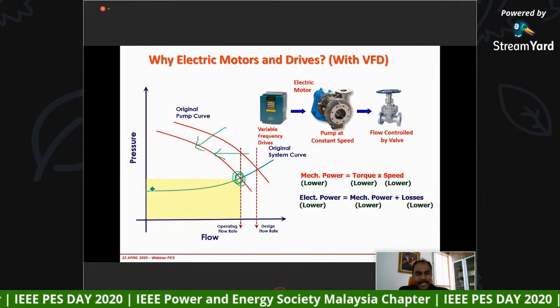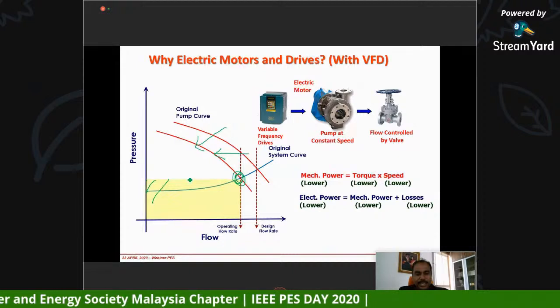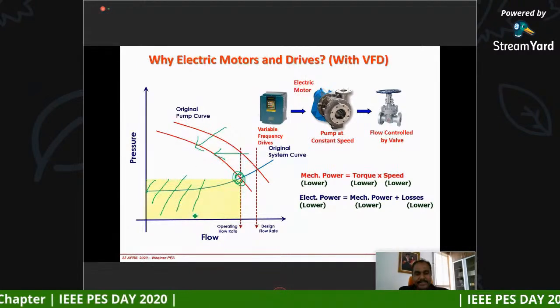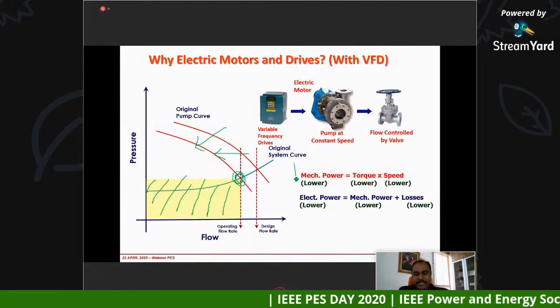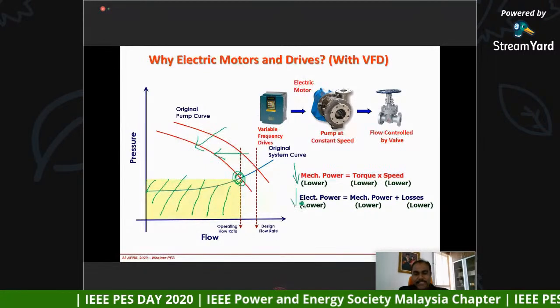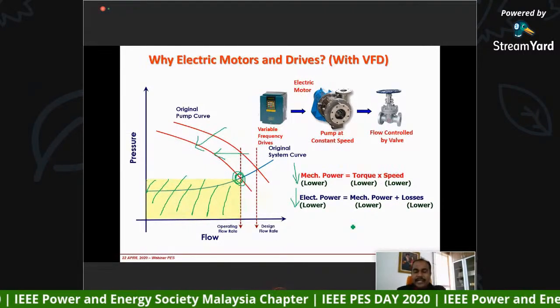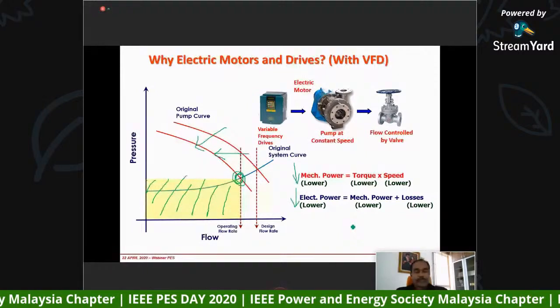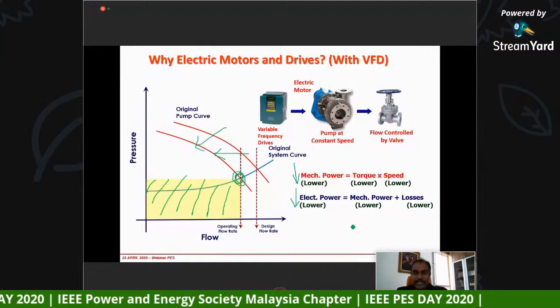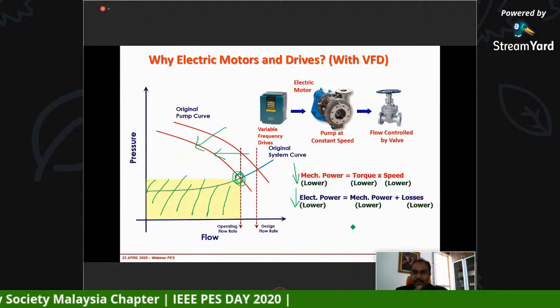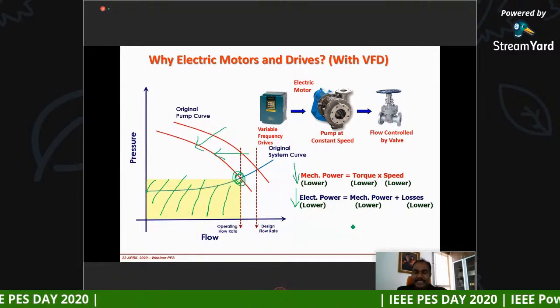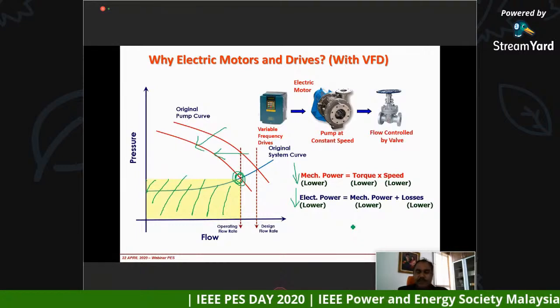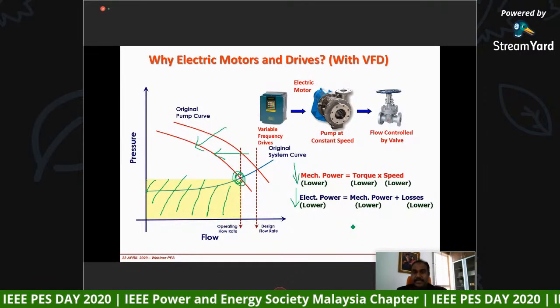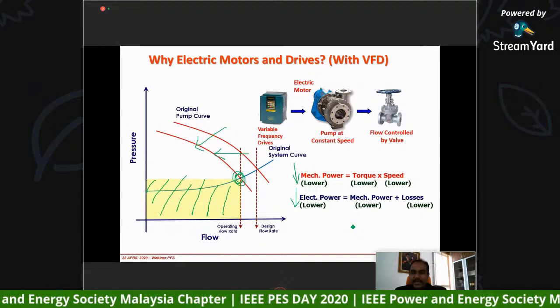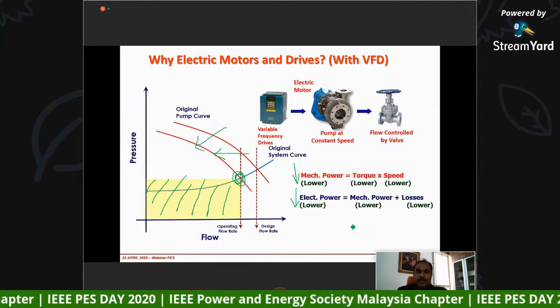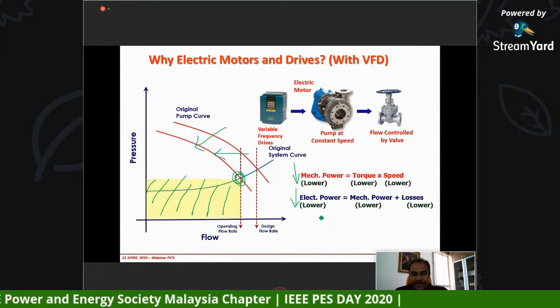And again, if you notice, the shaded area is going to be smaller. That means the mechanical power is going to get smaller. Okay, as you can see here, the mechanical power is actually reduced. That actually will reduce the electrical power. So this is how we actually save the energy. Okay, this is how we can actually save the energy in an electric motor system. But then, provided you have a system where it requires some changes. In this case, there's a change of flow. Then yes, okay, the application, the pump system in this case requires change of flow, and therefore a variable frequency drive will definitely help you to save on the energy.